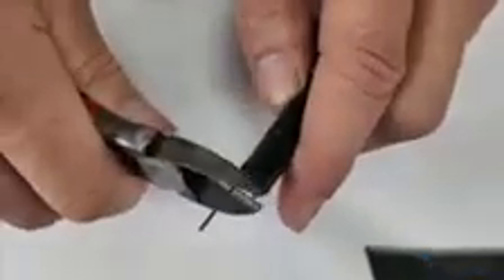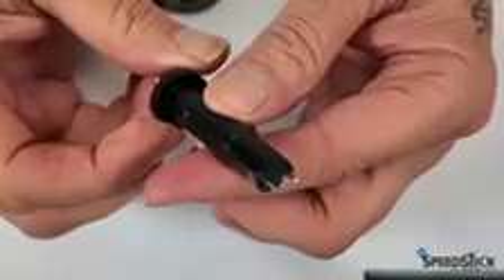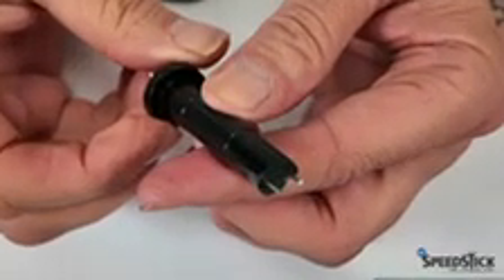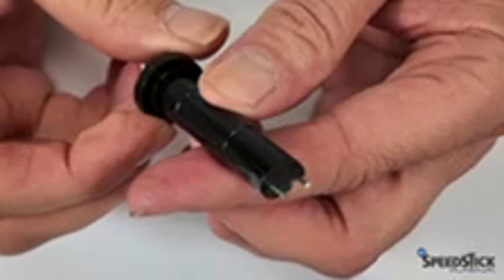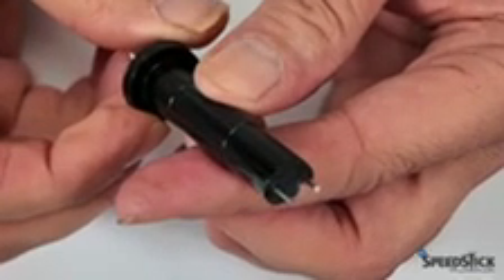Now you have a shorter probe. It'll fit in a 9,000 or a 12,000 unit, and we've seen on Daikin and some other units where it could hit the coil and not seat in the tray. If that happens, you'll have to trim that back.